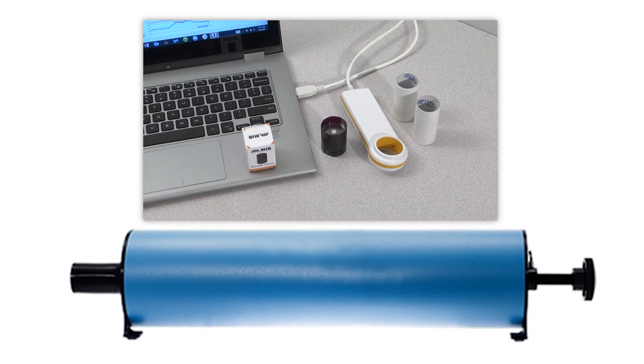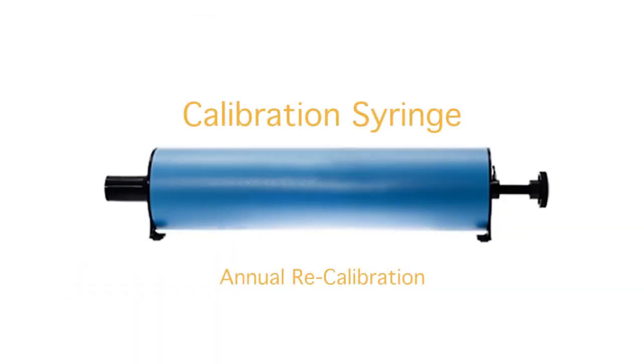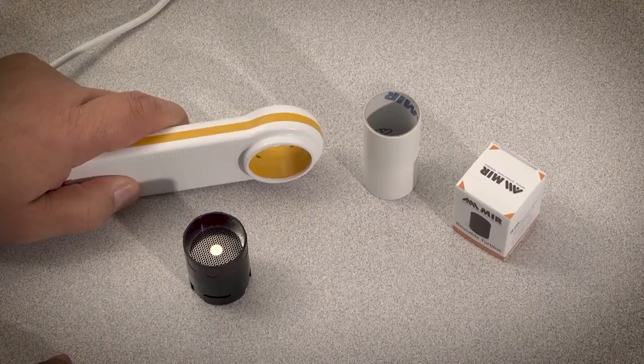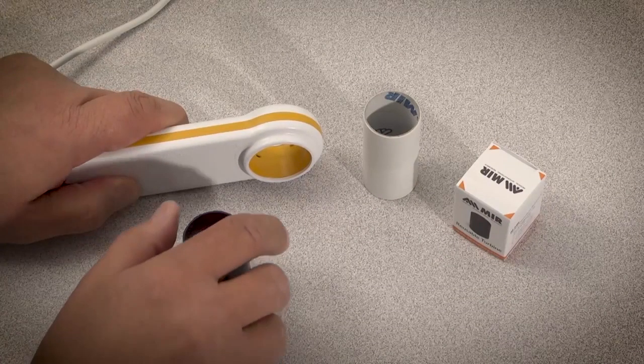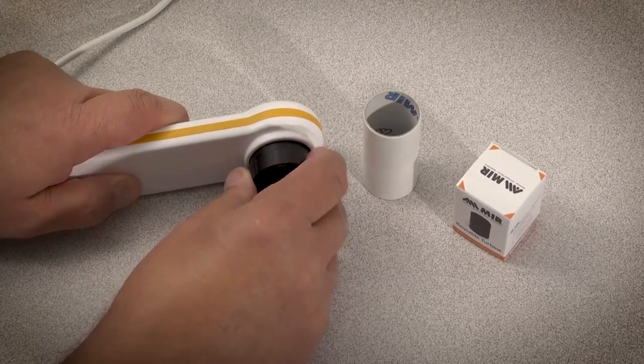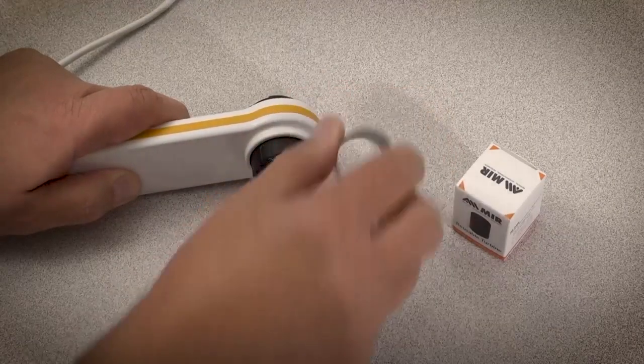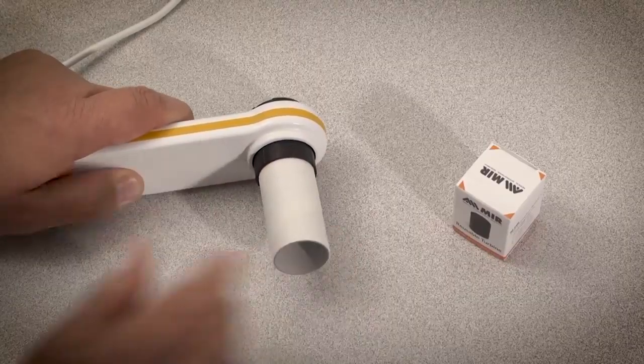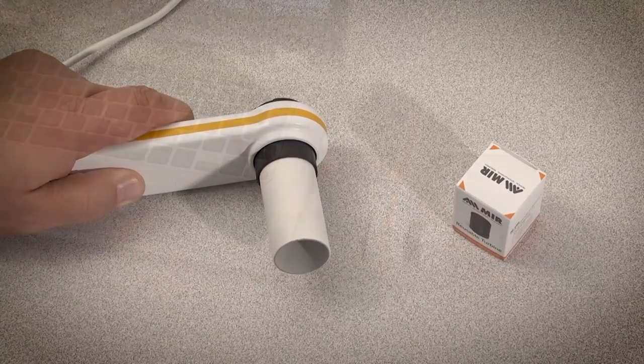To do the calibration check, you will need an MIR spirometer, a reusable turbine, a 3-liter calibration syringe, and winspiroPRO software. Remember that the calibration syringe needs to be sent back to its manufacturer once a year to be checked and recalibrated for accuracy. To begin the calibration check, first insert the reusable turbine into the flow meter and then insert a cardboard mouthpiece into the reusable turbine.